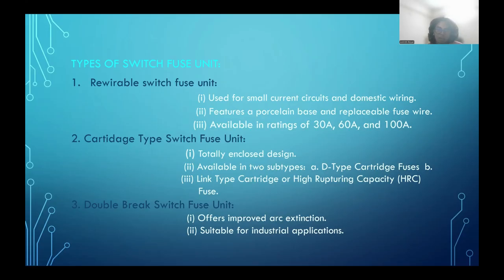Number two, cartridge type switch fuse unit. Totally enclosed design. Available in two subtypes. One, D-type cartridge fuse, and two, link type cartridge or high rupturing capacity fuse, which is also known as HRC. The third type of switch fuse unit is double break switch fuse unit. It offers improved arc extinguishing, suitable for industrial applications.